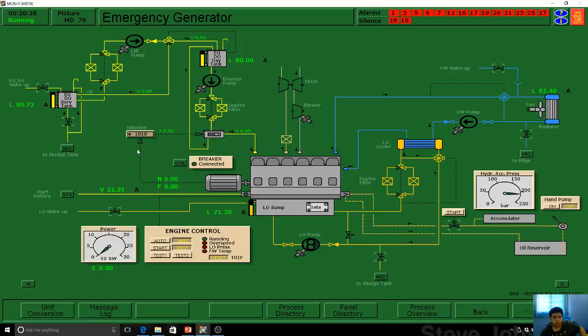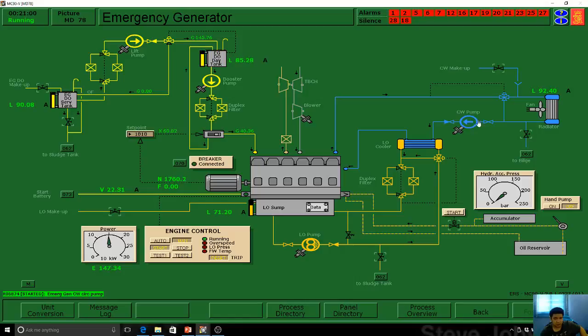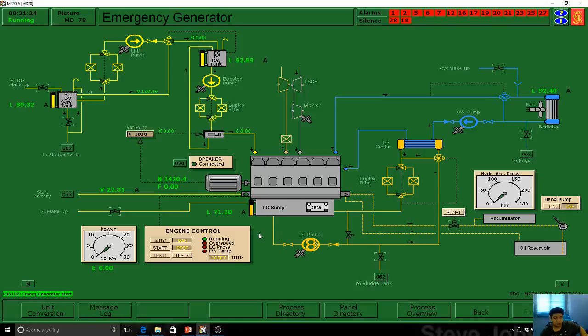Now we're going to start the generator. First, you can start it with the hydraulic accumulator. In the Kongsberg simulator, you just switch it on and press start — after checking all systems, including manual stop. As you can see, it changes colors and the hydraulic accumulator pressure drops. The lift pump comes on, it starts, the status shows running, and then it gets power. Now let's stop it — there are three methods to start it and I'm testing all three. It stopped — the turbocharger stops too.